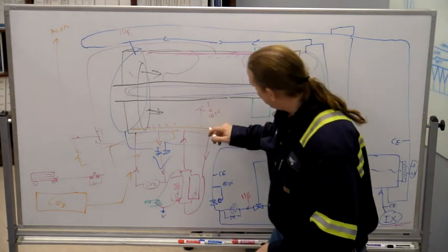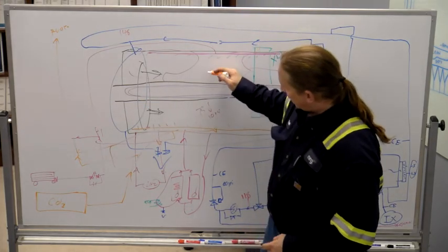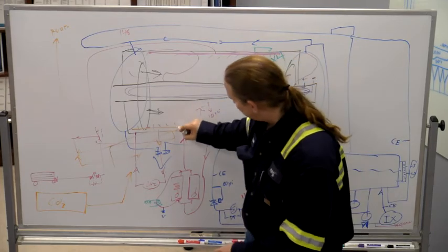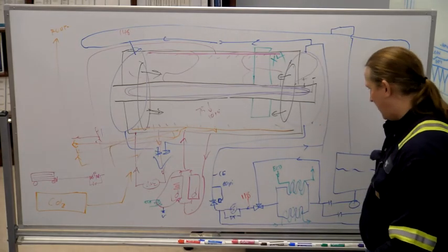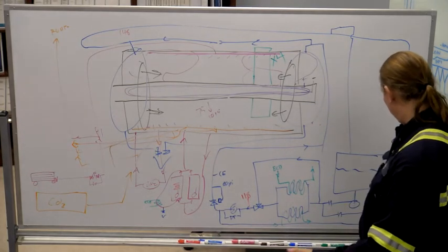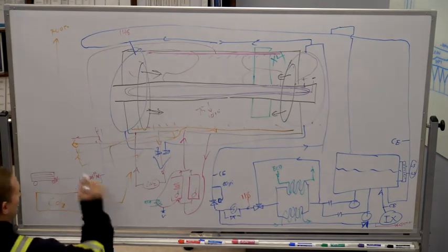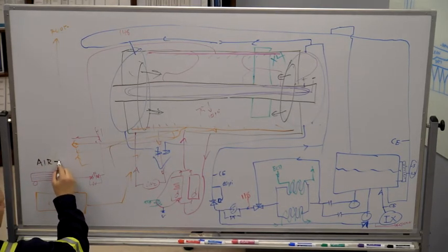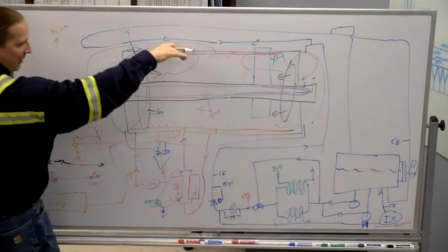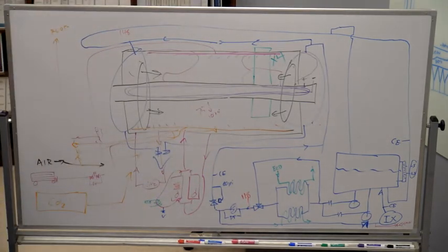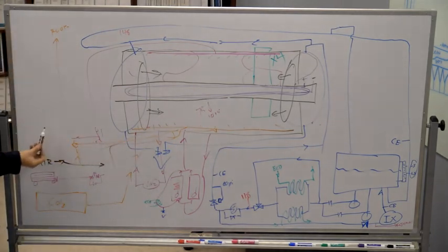So then we change our lineup. We were adding CO2 on the bottom. We were venting hydrogen out the top. Now the whole thing is full of CO2. And we are going to vent CO2 out the bottom. So we line that bottom up to the vent. Then we fill it with air. So compressed air goes into the fill line, goes into the top, and pushes the CO2 out the bottom. And so the bottom is lined up to the analyzer and then to the vent and then on out the roof.